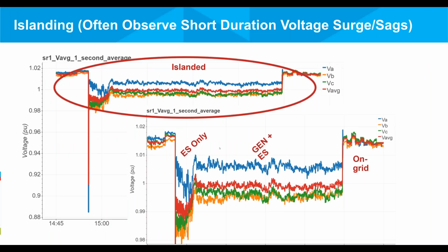Here's another example of an unintentional islanding that occurred. This occurred in October of this year, 2019. Unlike the last example, the energy storage was not fully charged, because we had just conducted maintenance on it, so it was at a lower state. Once the fault occurred upstream of the smart homes, energy storage tried to pick up the load initially, but the voltage was swinging back and forth, and as a result, the generator picked up the load.